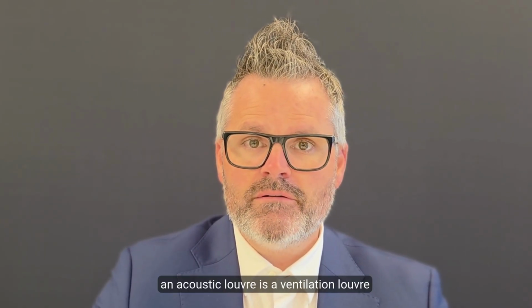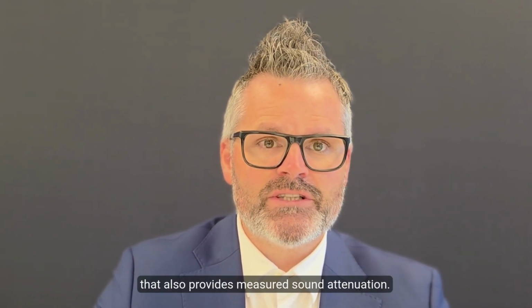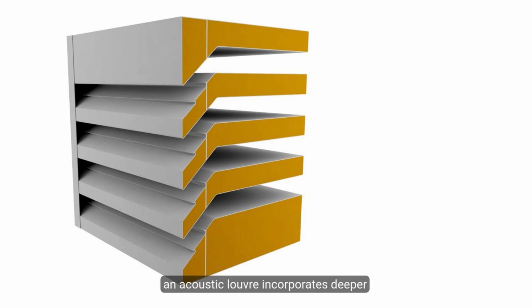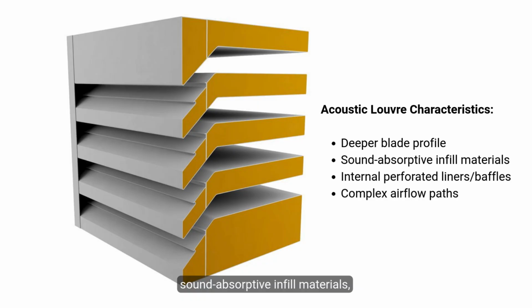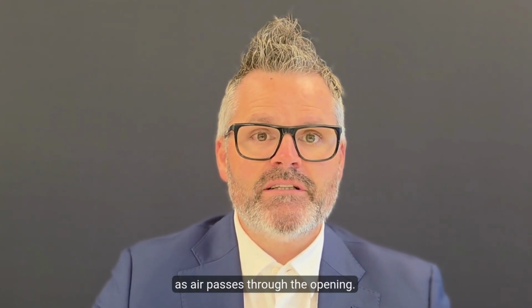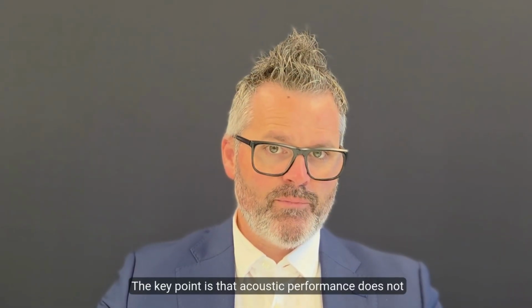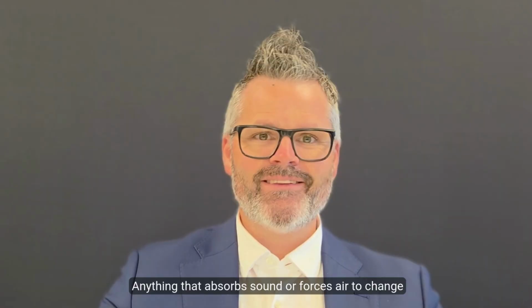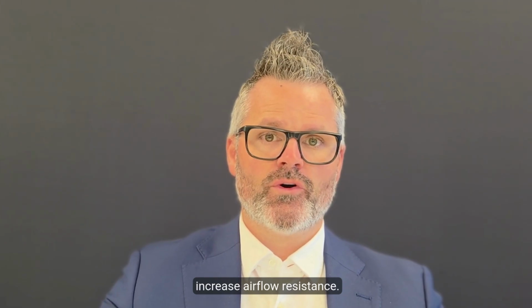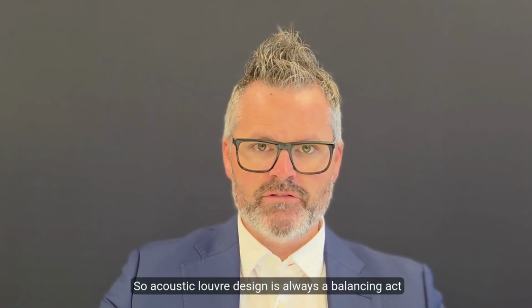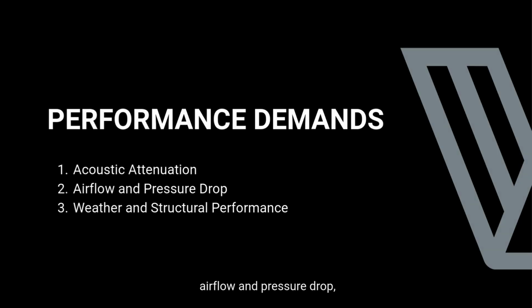At its simplest, an acoustic louver is a ventilation louver that also provides measured sound attenuation. Unlike a standard rain defense louver, an acoustic louver incorporates deeper blade profiles, sound absorptive infill materials, internal perforated liners or baffles, longer and more complex airflow paths. These features are designed to reduce the transmission of sound energy as air passes through the opening. The key point is that acoustic performance does not come for free. Anything that absorbs sound or forces air to change direction will also increase airflow resistance. So acoustic louver design is always a balancing act between competing requirements. There are 3 main performance demands that must be addressed together: acoustic attenuation, airflow and pressure drop, weather and structural performance. Let's look at each of these in turn.